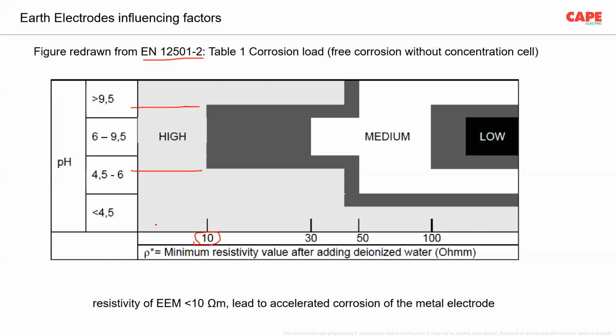What does it mean? Imagine you have a 100 ohm meter soil and you put an earth enhancing compound of, let's say, 0.2 ohm resistance in and around that particular earth electrode. In 100 ohm meter soil, probably you are getting 10 ohm resistance. With the additional material, you may get 8 ohm resistance. But this 2 ohm improvement in the resistance is actually degrading the life of your earth electrode, because the material in and around the electrode is highly corrosive. As a result, the chance of corrosion of your material is high. So any earth enhancing material having a resistivity of less than 10 ohm meter leads to accelerated corrosion of the metal electrode.